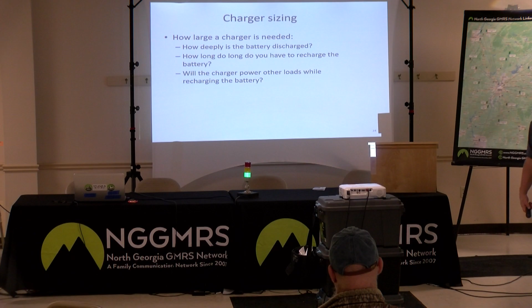We talked about this example, we were 96.6 ampere hours discharged from the battery. I'm going to take 2 days to recharge it. I took a day discharging it, so 2 days is not bad, that's double the discharge time. A number of places figure they'll recharge it in 4 times the discharge period.